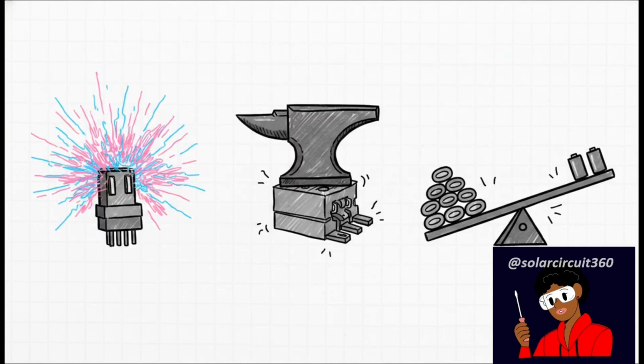And here is exactly why you cannot let this happen every single day. If you allow your charger to repeatedly force these emergency cutoffs, you are exposing your expensive hardware to severe, unnecessary electrical stress. Slamming the brakes on high current creates dangerous arcing at your connectors, extreme thermal stress on the internal MOSFETs of your BMS, intense wear and tear on mechanical relays, and it causes your charge controller to become highly unstable. Ironically, relying on this actually increases cell imbalance over time.